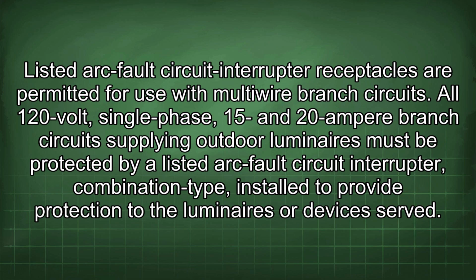All 120 volt, single phase, 15 and 20 ampere branch circuits supplying outdoor luminaires must be protected by a listed arc fault circuit interrupter combination type, installed to provide protection to the luminaires or devices served.